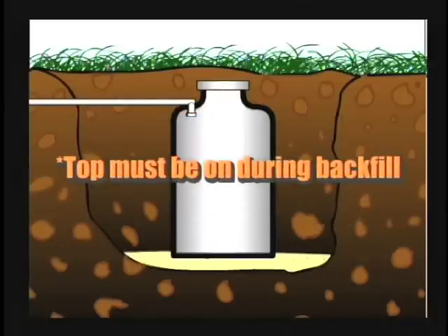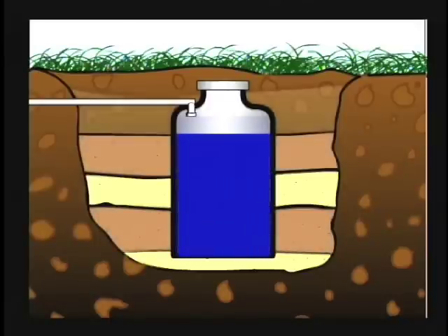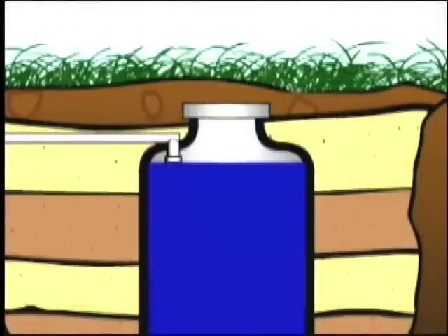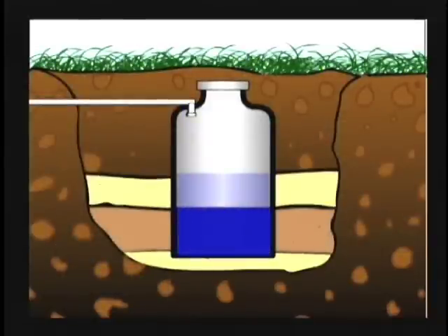The water in the tank will keep the soil from crushing the tank walls as the backfilling is performed. Do not overfill the tank or it will bulge. The water and soil provide balancing forces during the backfilling. Backfill the tank up to the water elevation using pure native soil without rocks.